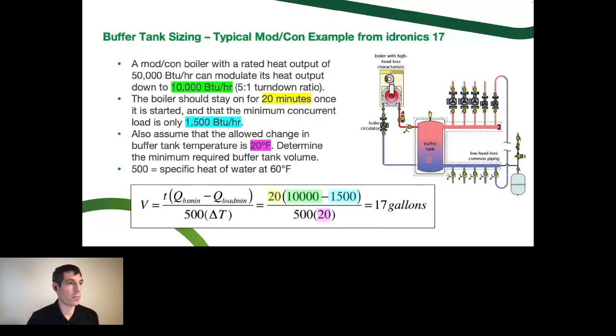Probably not. We probably want to shoot for something like 140 degrees that can fall to 120 degrees, so we still have some usable energy in there. That might be a good example. So in that case, we'll have a 20-degree delta T. So all of this sizes out to a 17-gallon buffer tank.